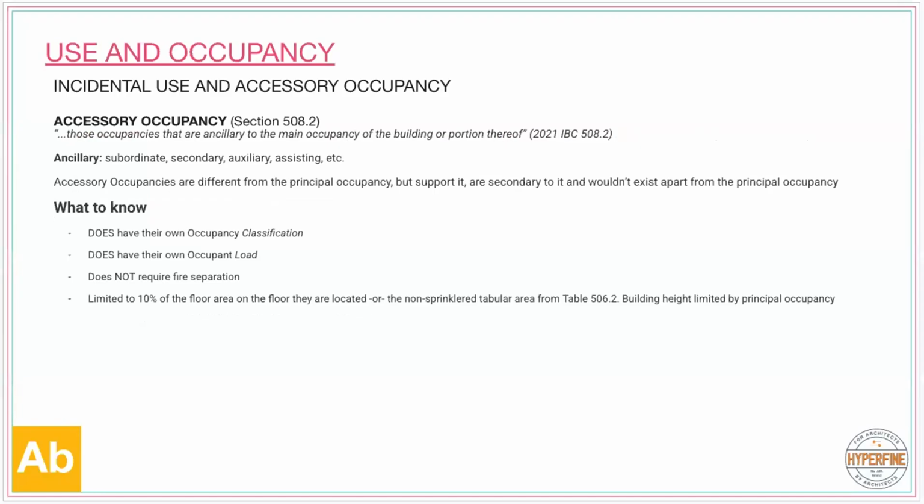So it's incidental use and accessory occupancy. An accessory occupancy is very similar in that it's an occupancy that's secondary or subordinate to the main occupancy of the building or that portion, in support of it. But they're different. An accessory occupancy does have its own occupancy classification. It does have its own occupant load, but it does not require fire separation.